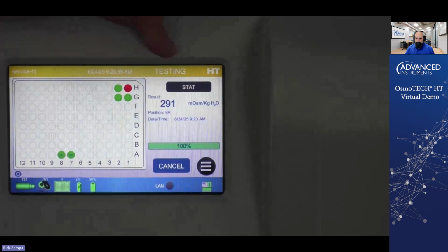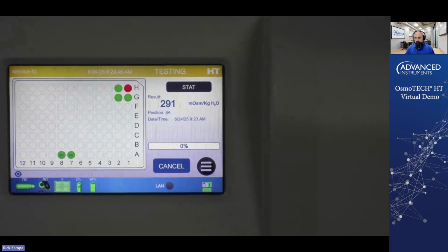Okay, and so we got a 291 on our next sample, so that's great to see. So just as a note here, I mentioned that we have the evaporation covers. I had loaded up this sample a little over an hour ago and put the evaporation cover on with the 290 reference solutions. You see we got a 290 and a 291. So you can see, yes, a little over an hour, there was absolutely no evaporation in the system by putting that evaporation cover on, which shows you exactly what you want to see.